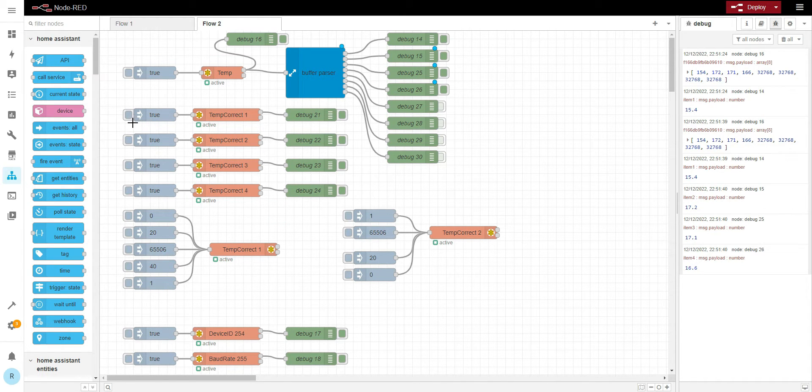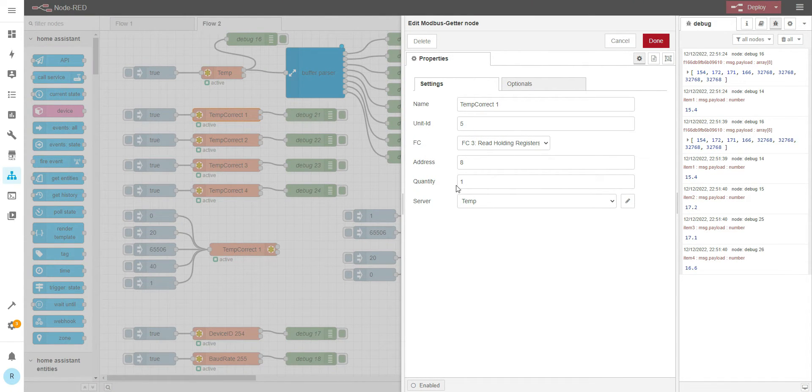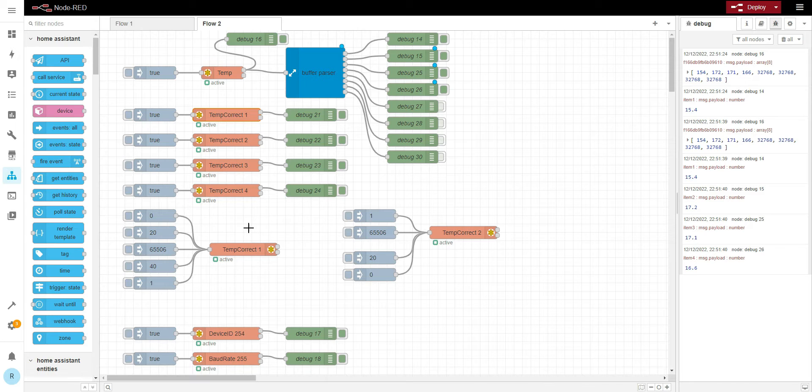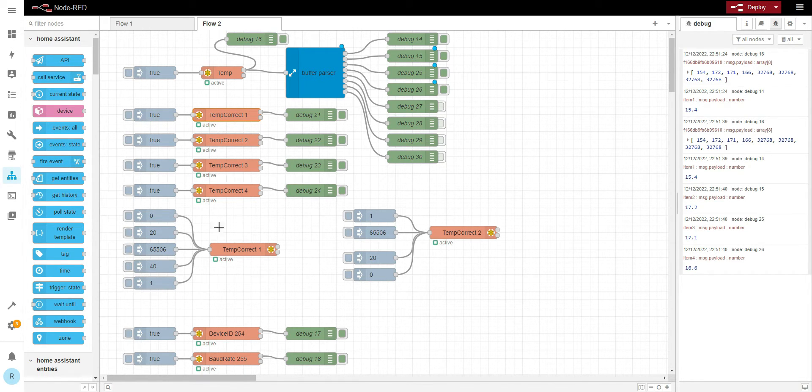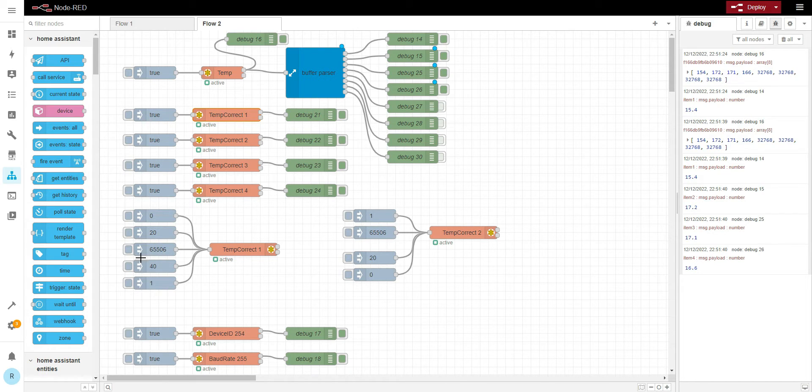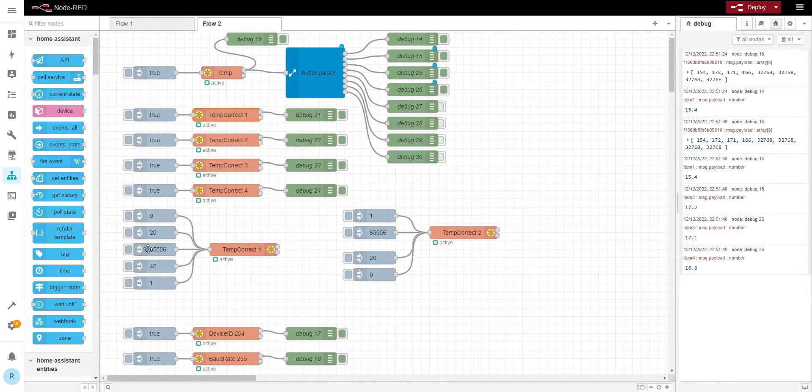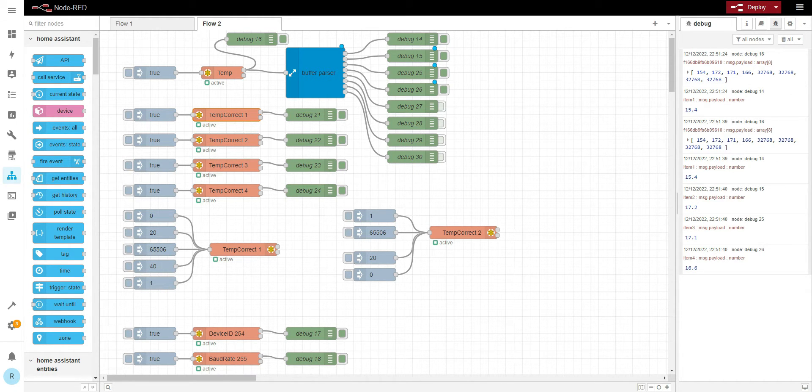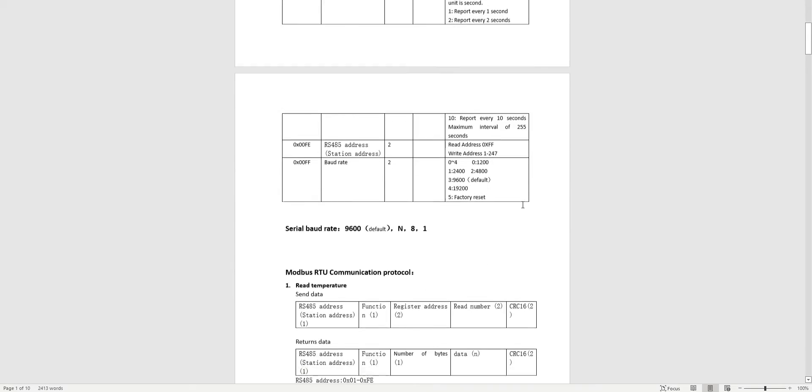Let me show temperature correction. The same thing, read holding registers. How we correct the temperature is exactly the same way as the previous one, but I'll explain in a minute why this is 65,506. It means we're correcting the temperature with minus 3.